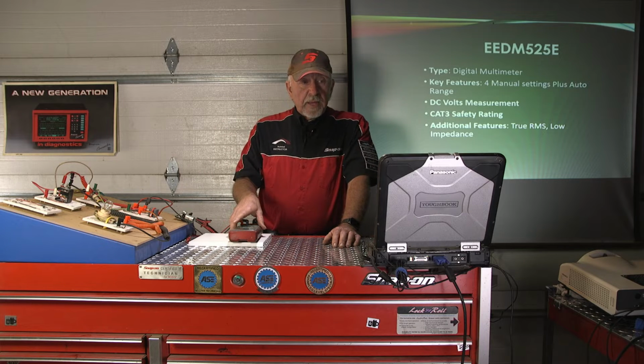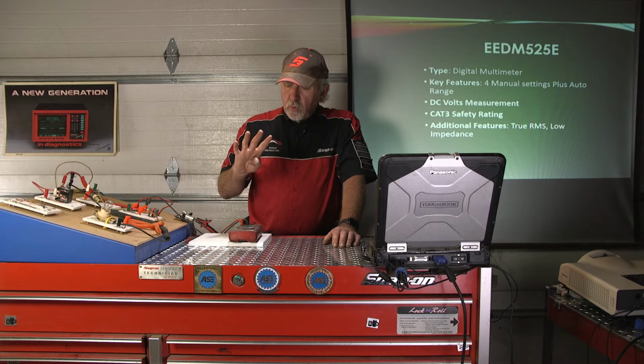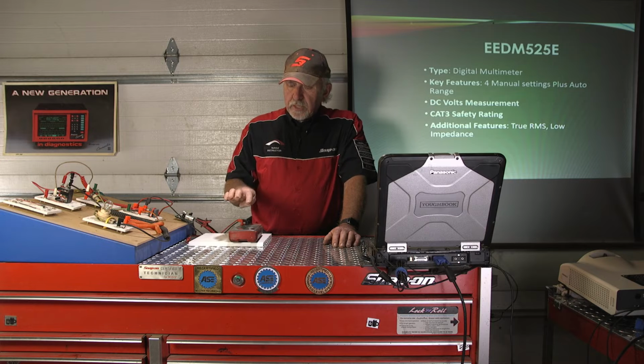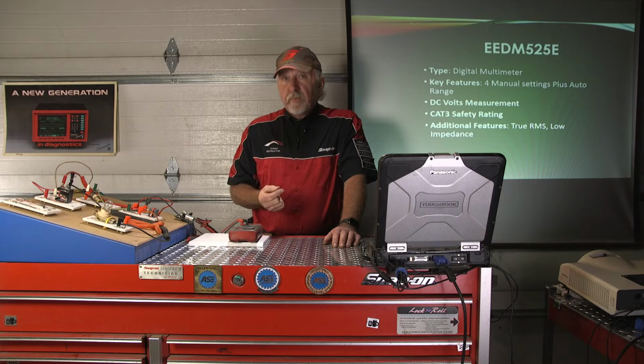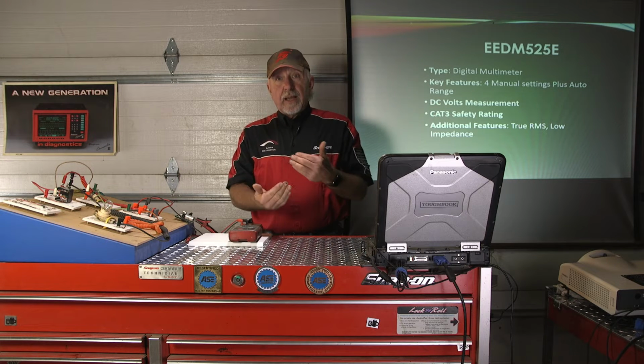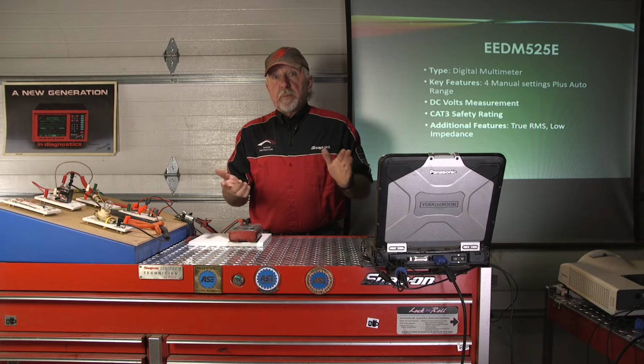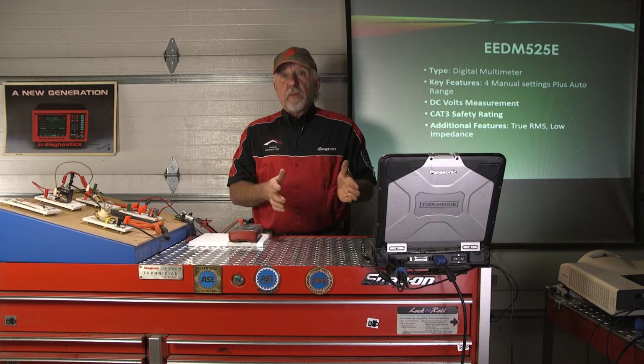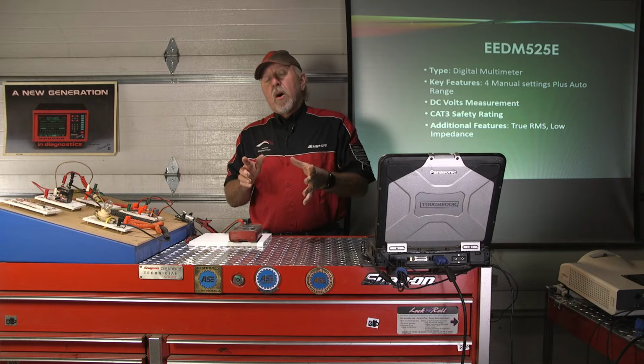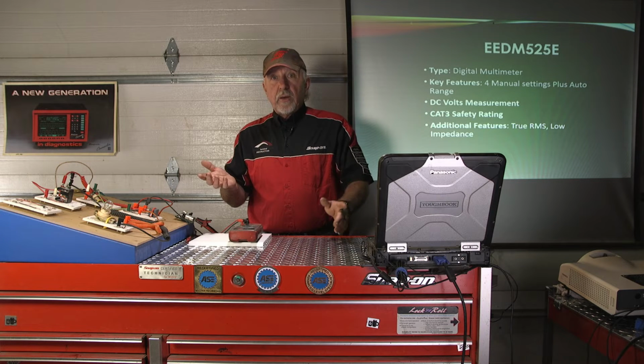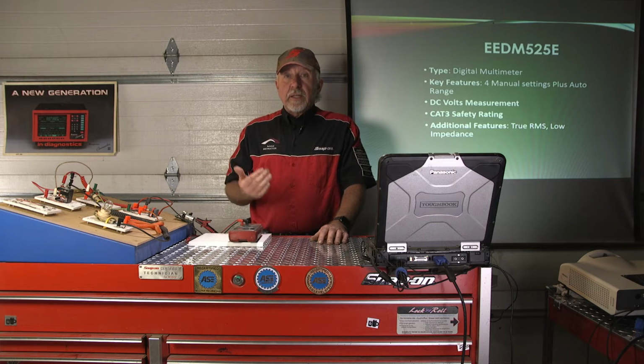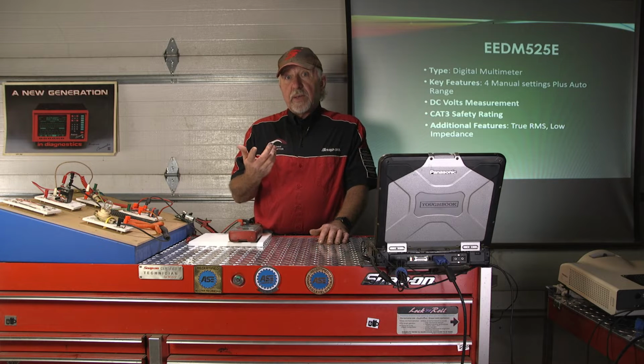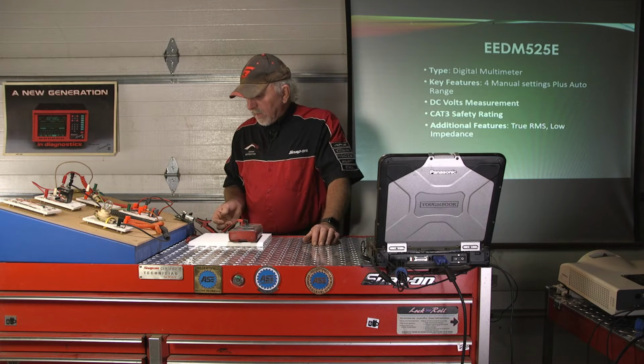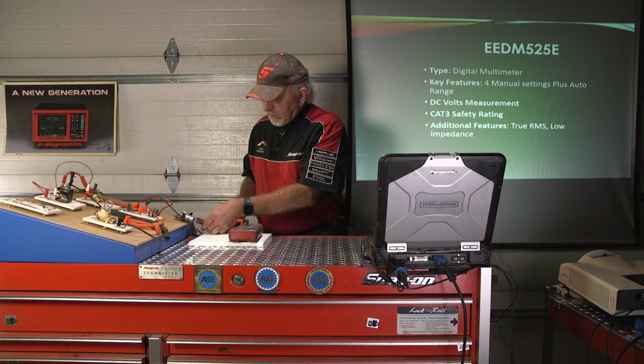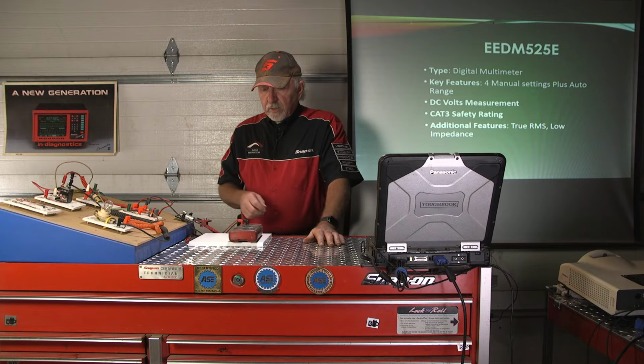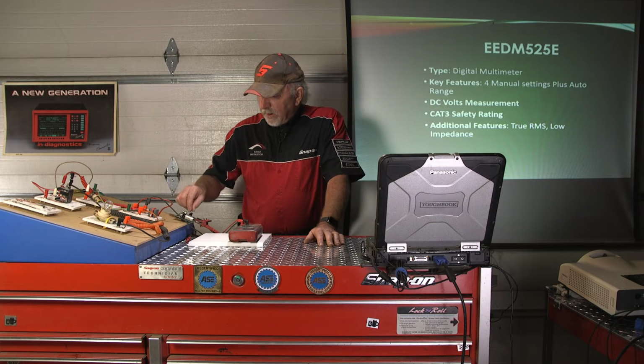A couple things to mention: it has 4 manual ranges plus the 1 auto range. From a testing standpoint, my experience has been to typically stay with the manual range. Auto range works if you have absolutely no idea what you're going to be up against, but the hunting of the meter itself can be distracting from a troubleshooting standpoint. Let's go over here to our fixed duty cycle, varying frequency.